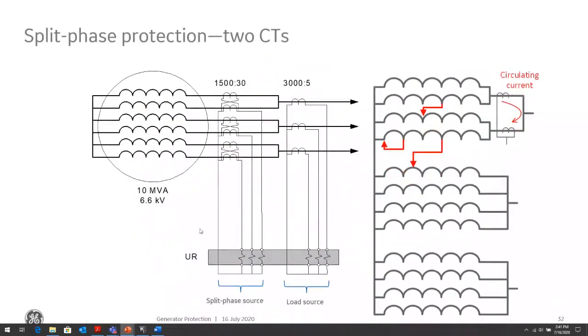The other split phase protection is using two CTs. So we need two CTs, one in each of the generator windings. And again, it's the same principle. If there's a circulating current within the winding, they add, whereas if there are load currents or external fault currents flowing, they will subtract.